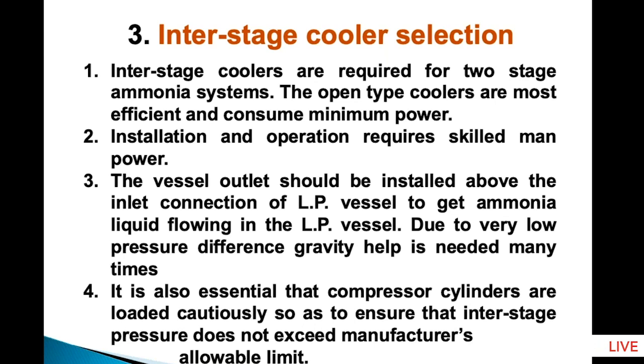So the pressure difference is very low, and it takes time to fill up the LP vessel many times because there is a pressure drop in the line from the outgoing of the interstage cooler to the incoming of the LP vessel. So in this line, to avoid the pressure drop, allow it to flow by gravity, and therefore this interstage cooler needs to be installed above the level of the LP vessel, which normally becomes 13 or 14 or 15 feet high, and many plant rooms are designed for a 10 feet high machine room.